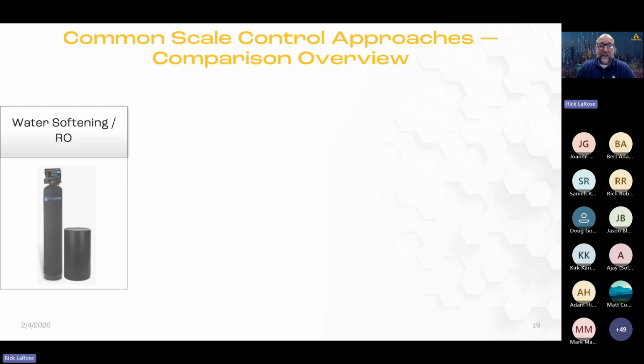The trade-off is you need a dedicated water softener, some space for that, ongoing salt replacement, membrane maintenance, water usage, backwash usage to flush those out, and operational oversight. We're not here to say you shouldn't be softening, but softeners have a place, and they can be a maintenance nightmare. Oftentimes I see them just turned off, people don't want to mess with them, they don't want to deal with them.